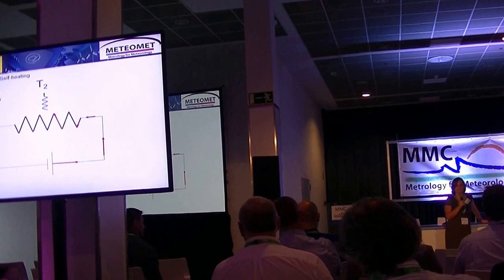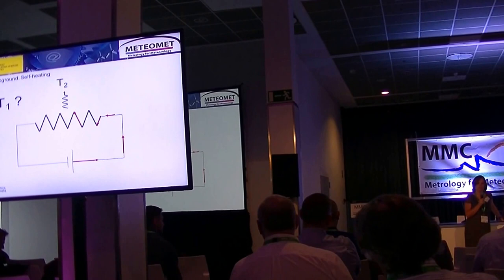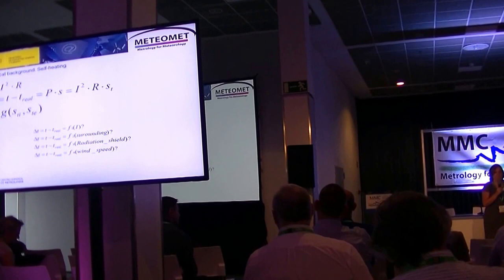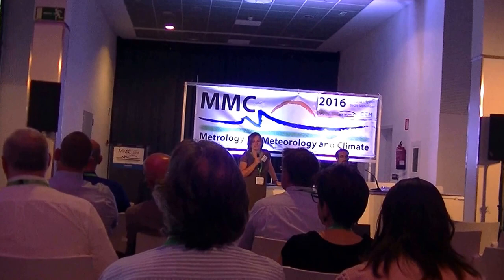So what is the difference between the real temperature and the temperature measured by the thermometer? This is what we want to analyze in this talk. The model states that the difference in temperature is a function of the square of the current, the resistor, and a self-heating coefficient.